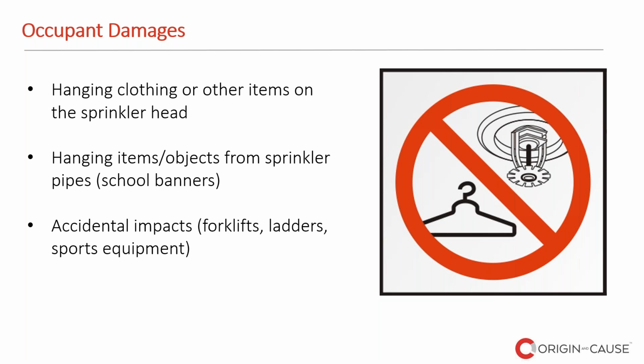So in my experience, this used to happen a lot in hotels with those exposed heads, and when it comes to my investigation, it is very important that we obtain the statements from all the parties involved, so the security personnel, the witnesses, the occupants as well, and the first responders, like a fire department, for instance. Other types of damages include accidental impacts, such as with forklifts, ladders, and sports equipment. So in an arena, you can have sprinkler heads, and if they're hit with a baseball or something, then obviously they can be damaged and go off.